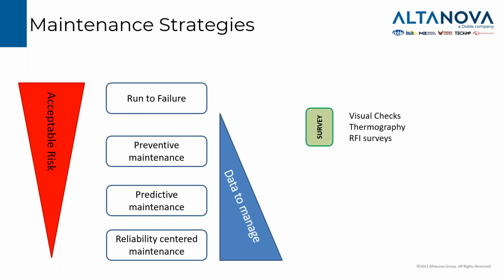For instance, we can have surveys, quite quick and easy checks of the asset that can be done simply by visual inspection or by standardized survey methods that we can have in a substation, like thermography or RFI. And if we want to have deeper information on the condition of the asset we're going to test, we can have an investigation step that can be performed online with partial discharge screening and partial discharge tests on a specific asset. So we can be a little bit more specific, and we can build a test around the asset.